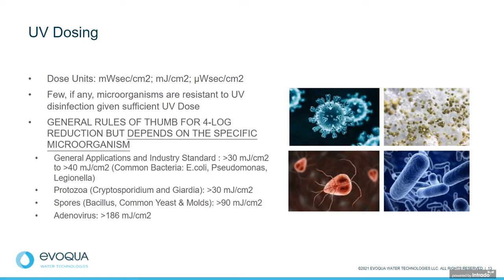They're all kind of equivalent units. Millijoules per centimeter squared is most often used. We know that very few microorganisms, if any, are resistant to sufficient doses of UV. General rules of thumb: every company seems to have their own guidelines for UV dose. It can be anything from the standard application of UV dose, which is 30 millijoules per centimeter squared, up to 40 millijoules per centimeter squared, which will give you a 4-log reduction of bacteria, E.